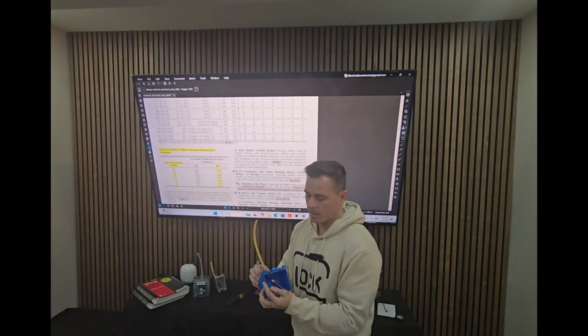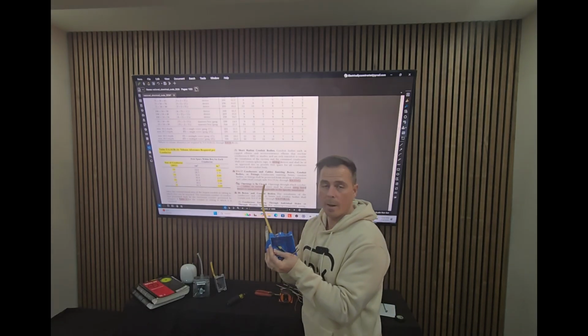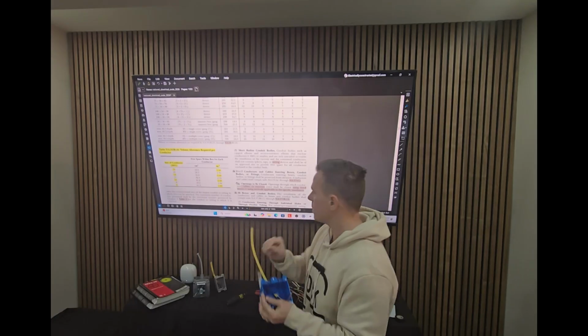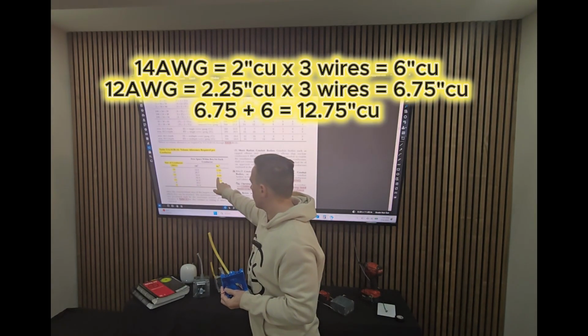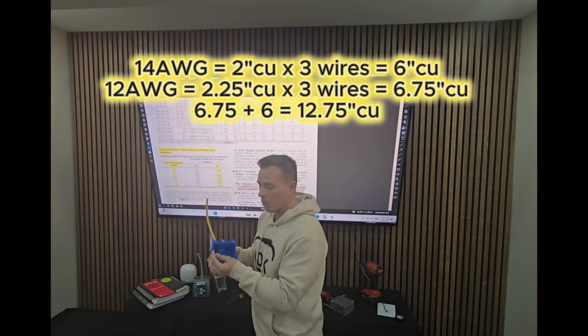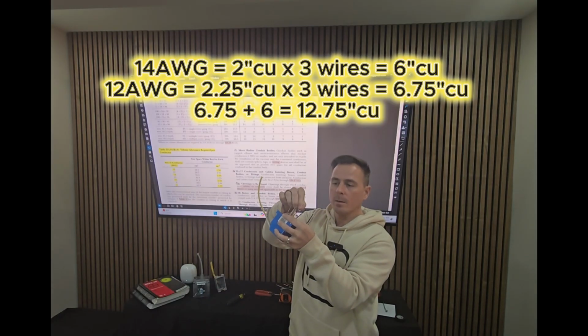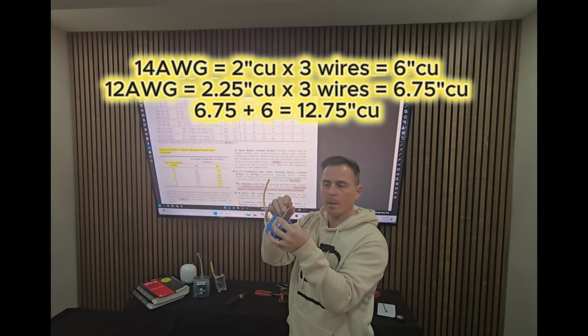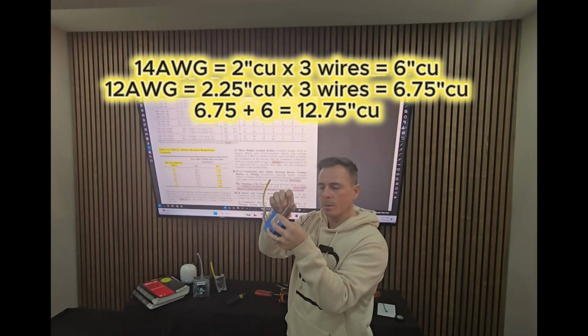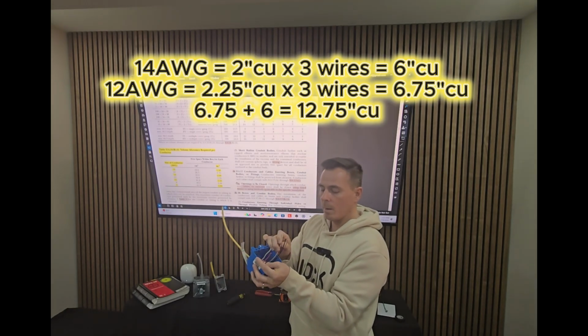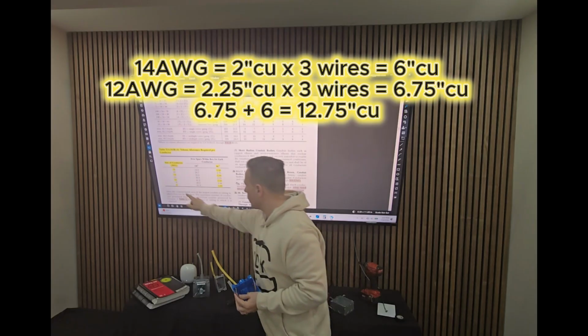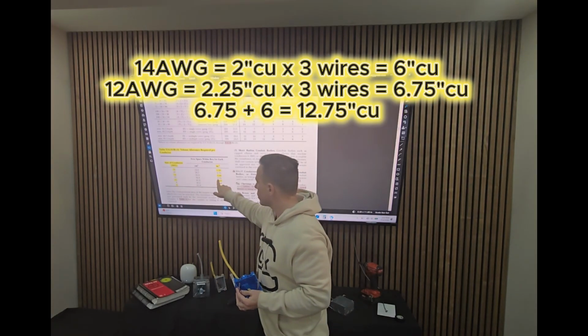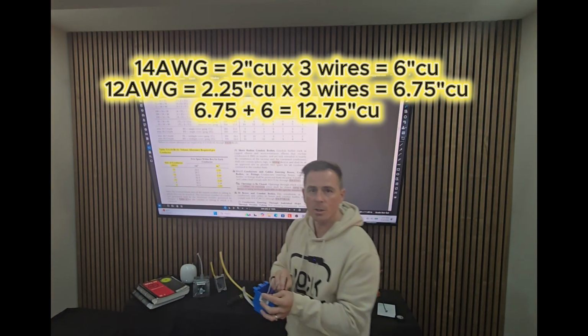All right, we're back. Okay, so let's go through it. We got 14/3. We're going to count that up first. 14 gauge wire equals 2 cubic inches per wire. So we got the white, we got the red, we got the black. That's going to be 6 cubic inches right there. And then we got our 12/2. 12 gauge wire equals 2.25 cubic inches per wire.